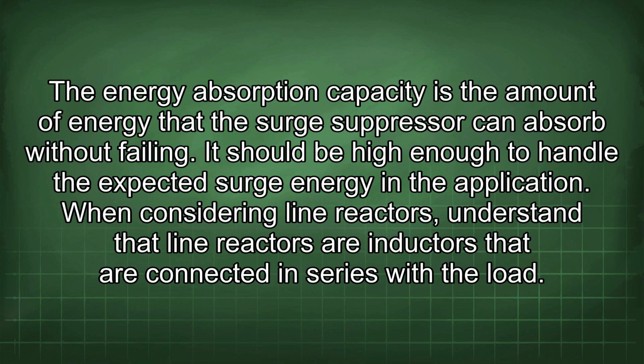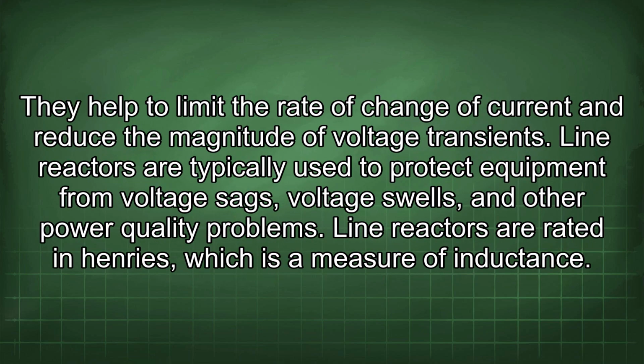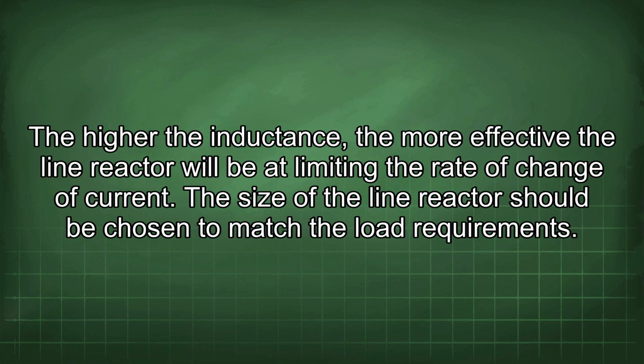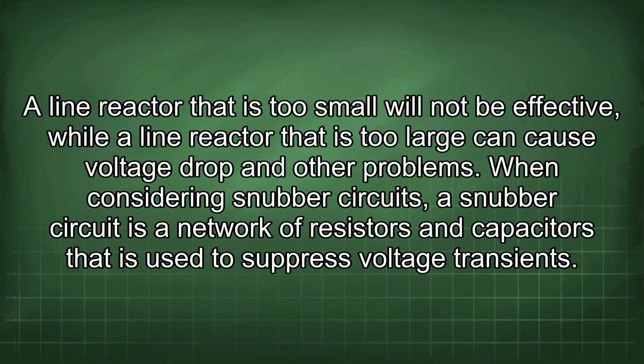When considering line reactors, understand that line reactors are inductors that are connected in series with the load. They help to limit the rate of change of current and reduce the magnitude of voltage transients. Line reactors are typically used to protect equipment from voltage sags, voltage swells, and other power quality problems. Line reactors are rated in henries, which is a measure of inductance. The higher the inductance, the more effective the line reactor will be at limiting the rate of change of current. The size of the line reactor should be chosen to match the load requirements. A line reactor that is too small will not be effective, while a line reactor that is too large can cause voltage drop and other problems.